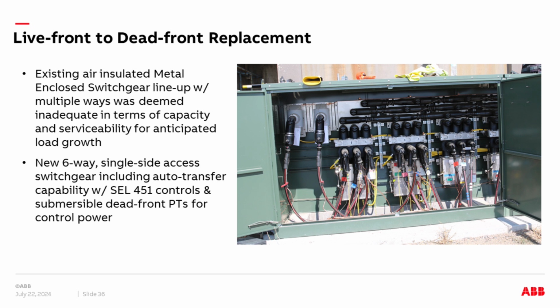Another application here is a large lineup. It's a 6-way with space for future growth. So you can see in this application, the individual ways are connected with rigid bus jumpers across the top of the gear. There's also two PTs to power the controls, shown there in the upper left, where the PT is also completely submersible, dead front, and uses a 200 amp elbow to tap primary power going into the PT, and then you get 120 volt out of the secondary.